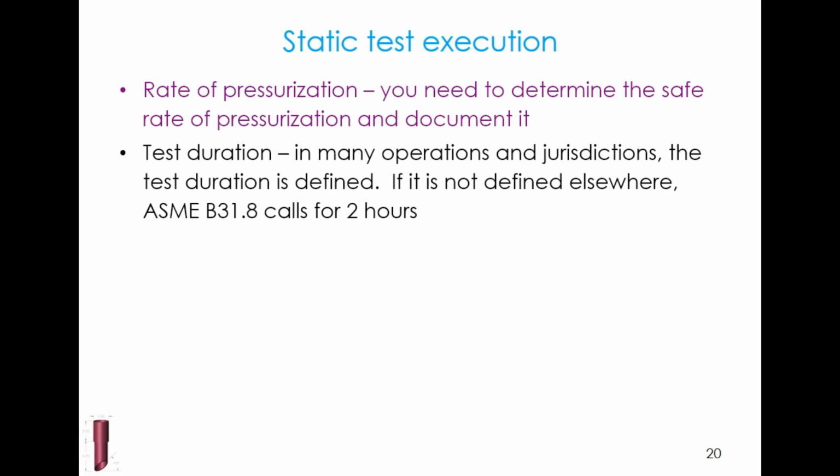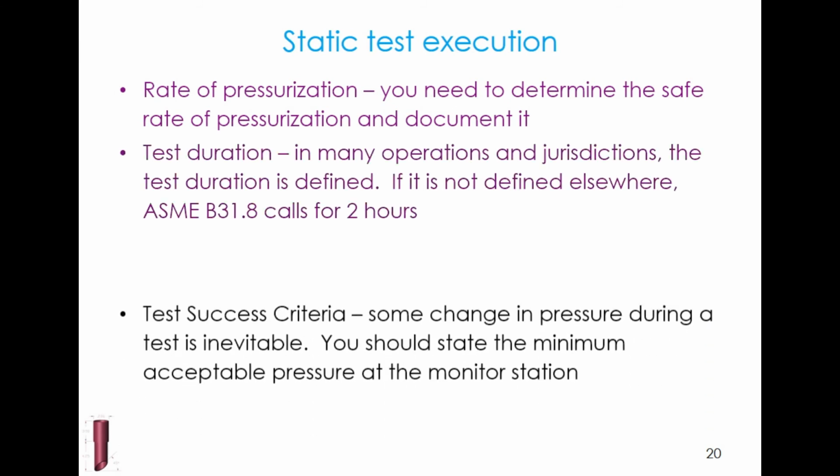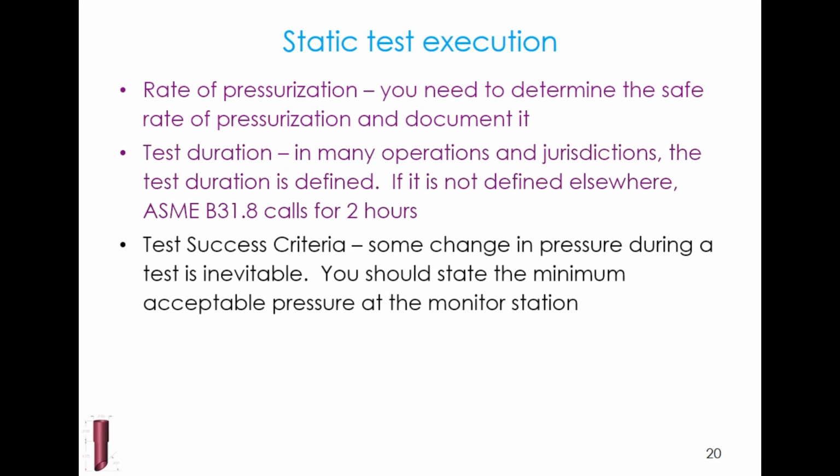A company will say all tests have to be for 24 hours. A jurisdiction will say all tests have to be at least 5 minutes. If it's not defined elsewhere, then the ASME B31.8, which is the gas code, calls for 2 hours. You need to define success.